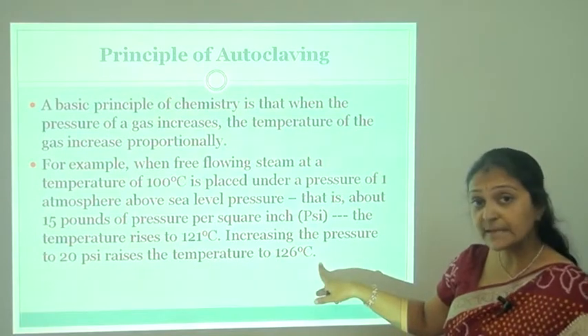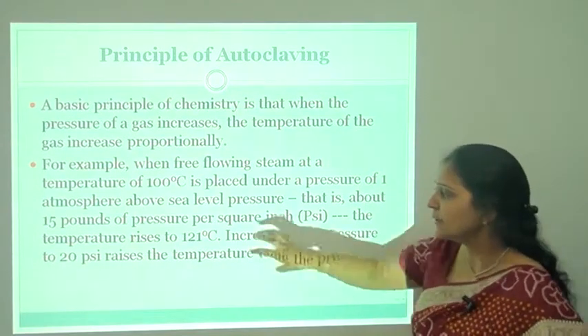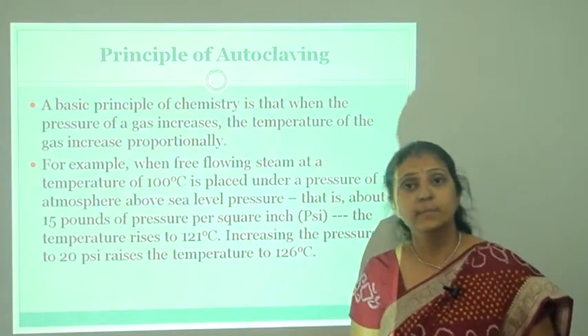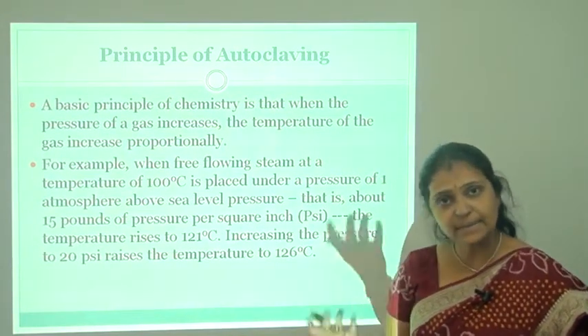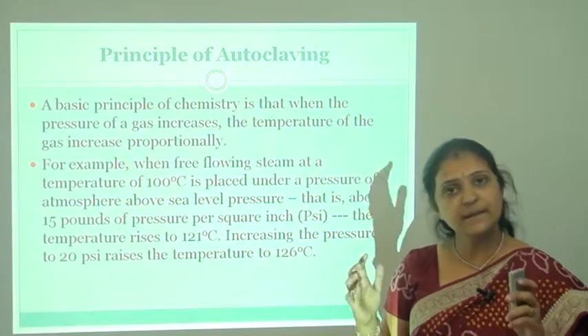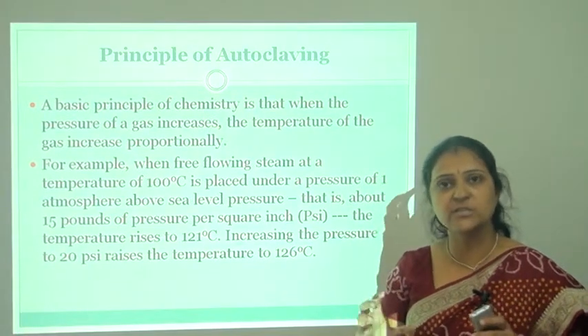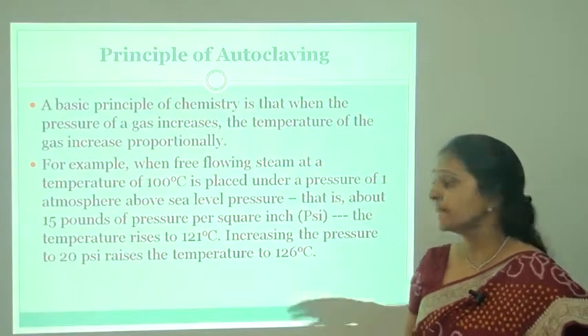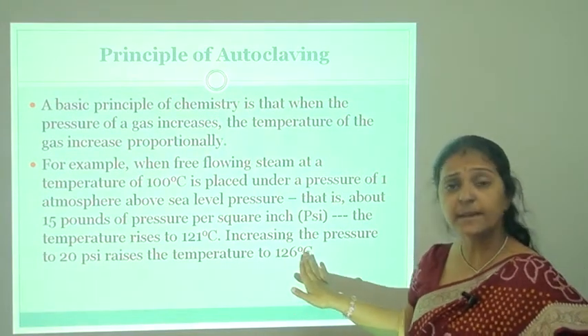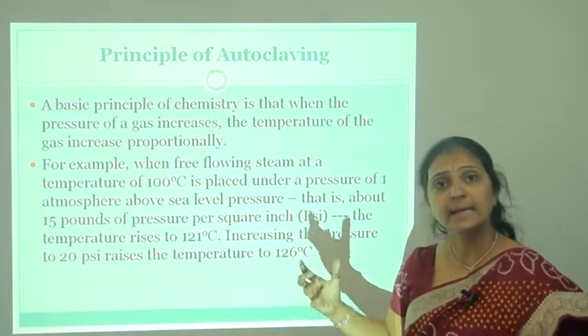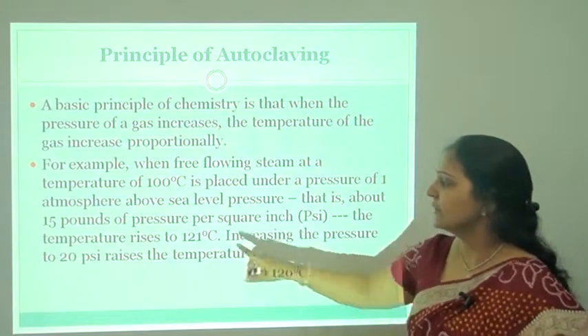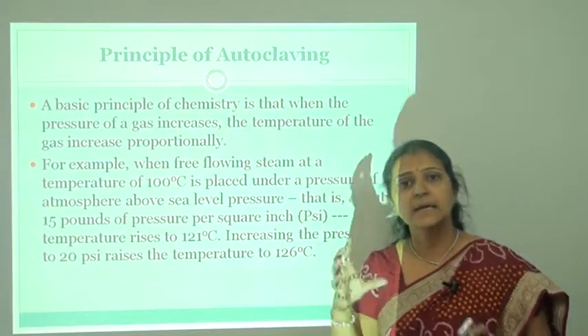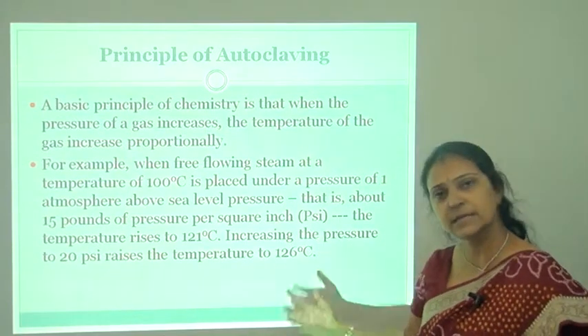Increasing the pressure up to 20 psi raises the temperature to 126°C. But why do we use only 121°C at 15 LB pressure? Because if we sterilize media in the autoclave, the medium composition or constituents should not be denatured. At higher temperatures, the media can be denatured. So 121°C, 15 LB pressure, and 15 minutes is fixed for sterilization of culture media.